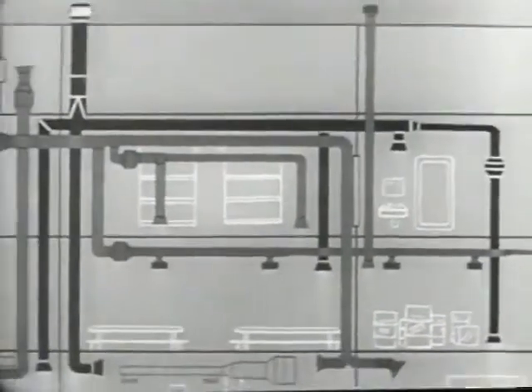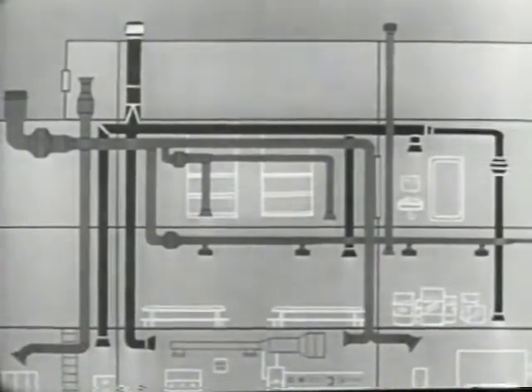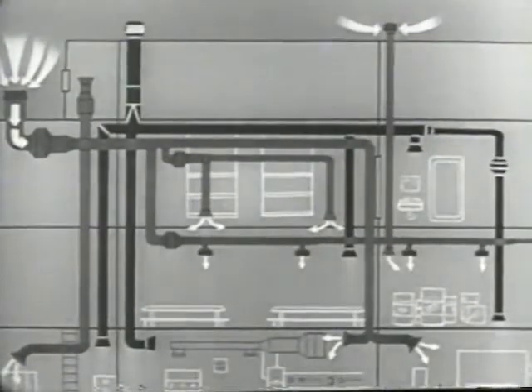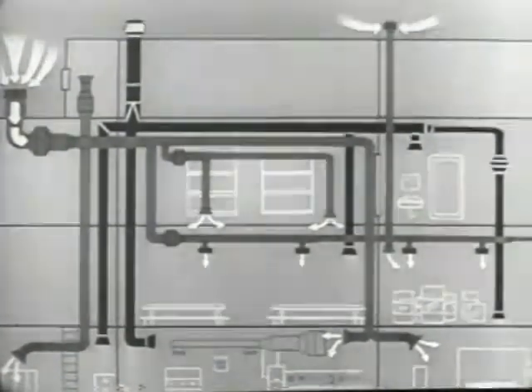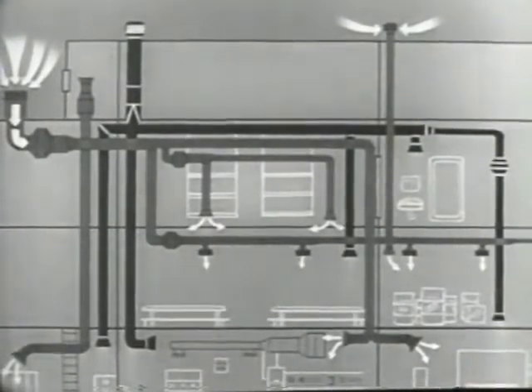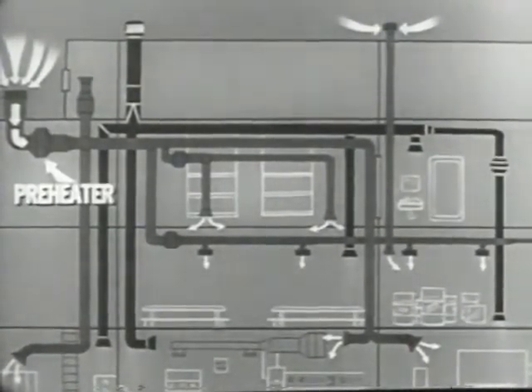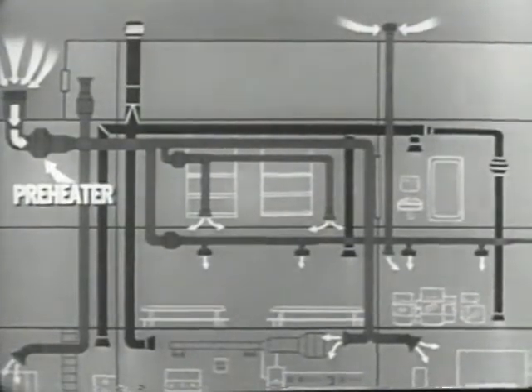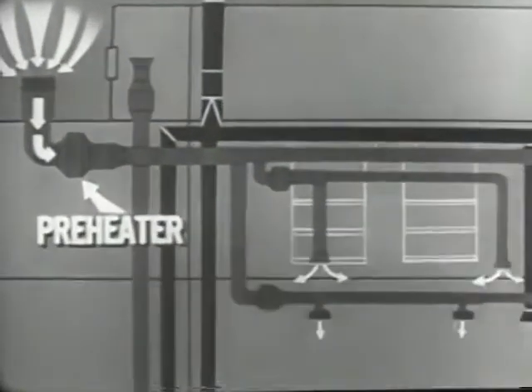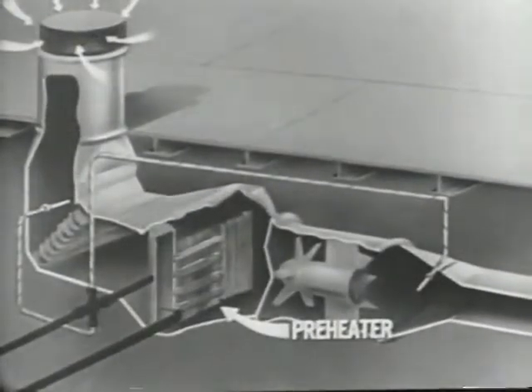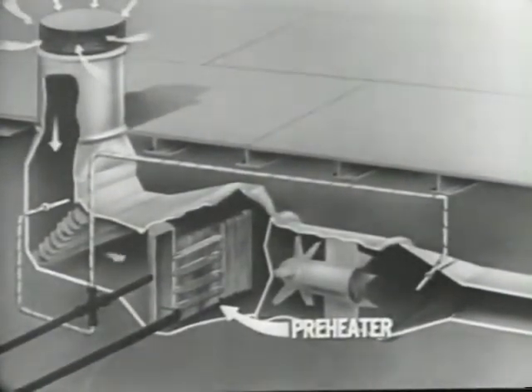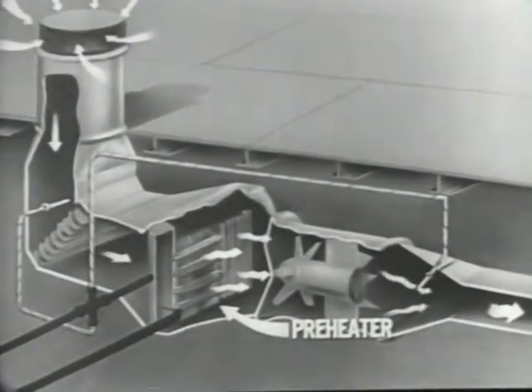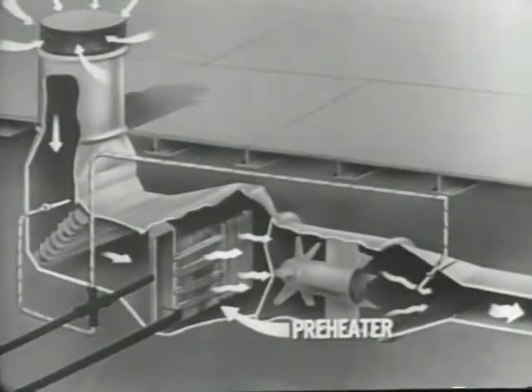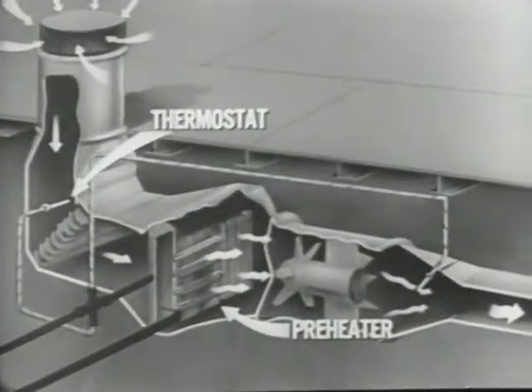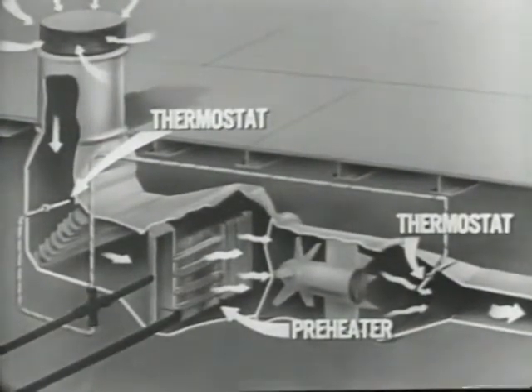Wherever practicable, the system which supplies air within the ship for ventilation also provides heated air in cold weather. The first stage of heating takes place in a preheater, which is installed upstream of the fan in the ductwork, usually near the intake. Air passing through the preheater is warmed as it flows by these steam-heated fins. The amount of steam entering the preheater is regulated by a control valve having two thermostatic bulbs, one on the inlet side of the heater and the other on the discharge side.